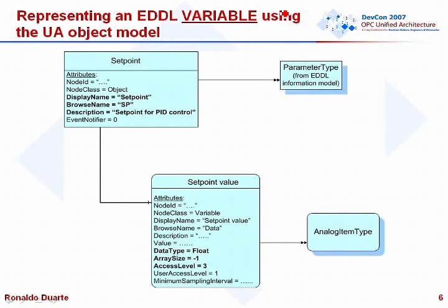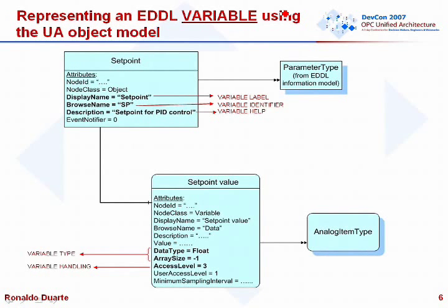The server accesses the EDD and fills the bold attributes with the information it finds. For instance, the information model tells me how to fill the description attribute for a parameter: go to the EDD and find the help string located there, then put that help string into the description variable. For the parameter value, go to the EDD again, get the type of the parameter, then fill the OPC UA node type accordingly. These nodes are interesting because they derive directly from the EDD.